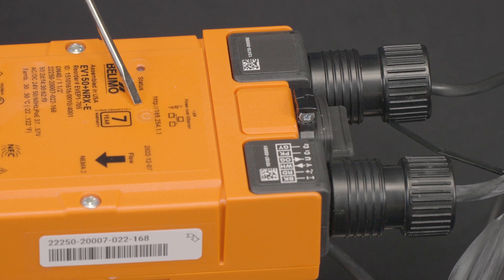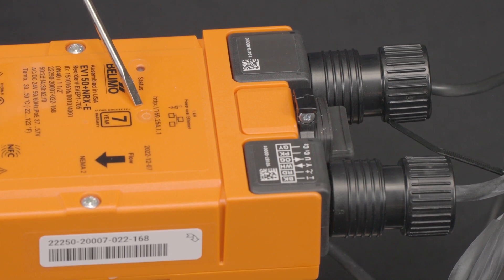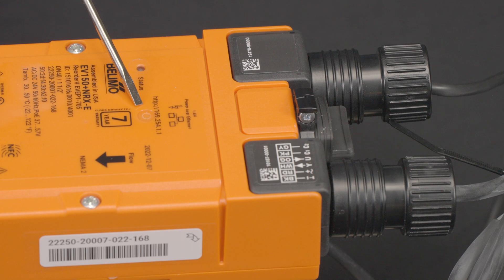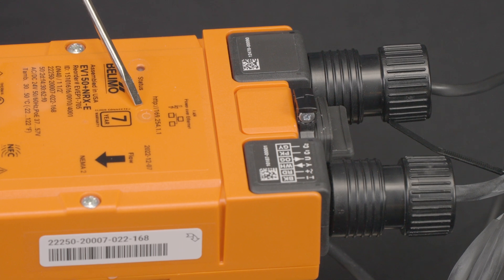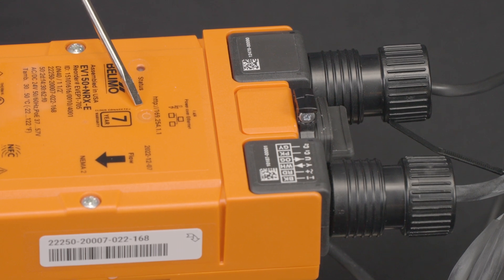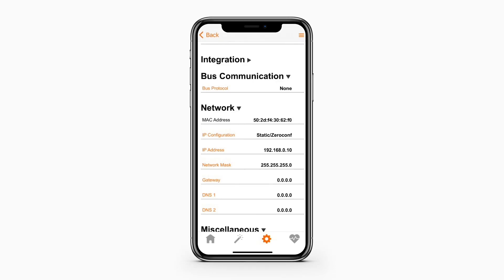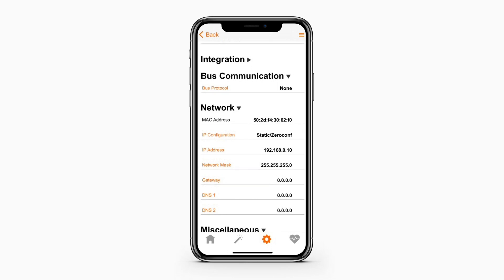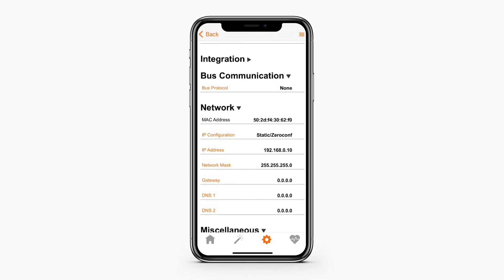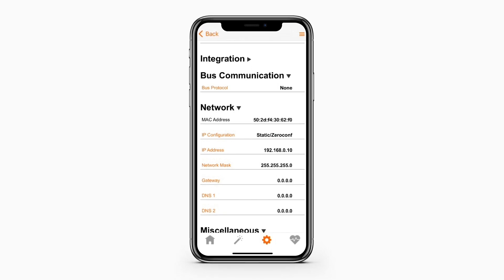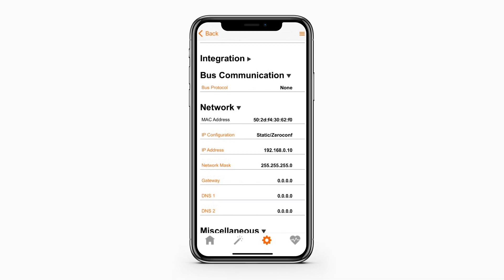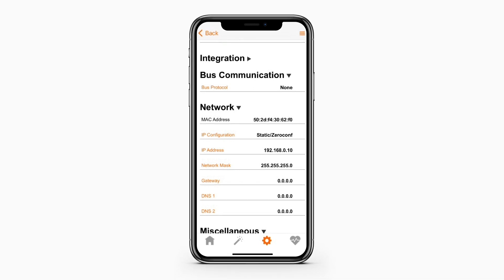You can employ the Zero config address, conveniently provided on a label on the device's logic module, or you have the option to use the Belimo Assistant app, which is compatible with most Apple and Android devices. This app uses your smartphone's NFC capability to connect with the logic module, allowing you to acquire the device's IP address seamlessly.